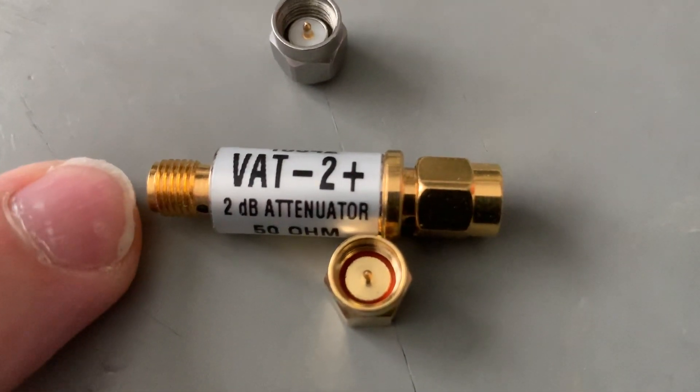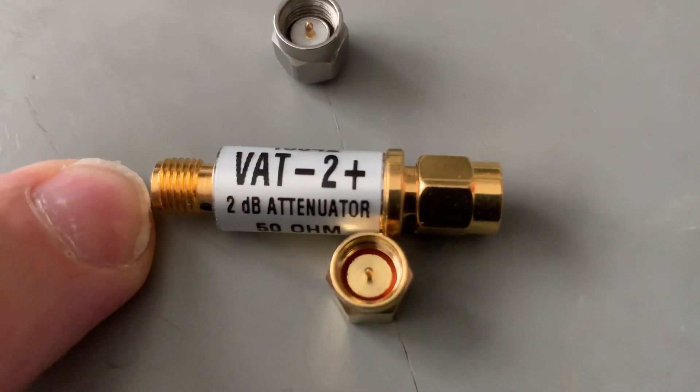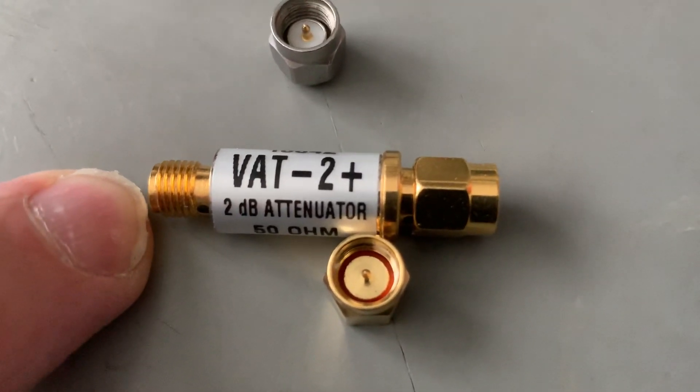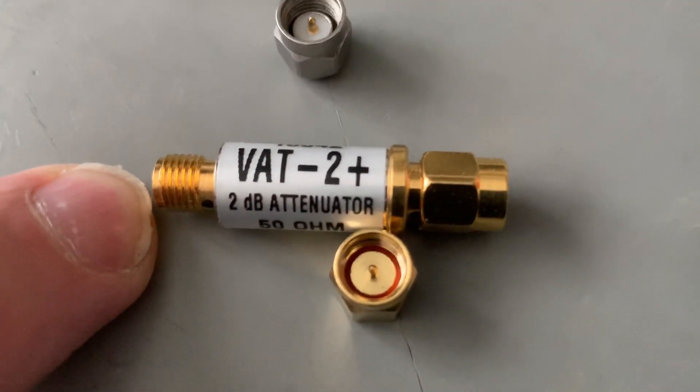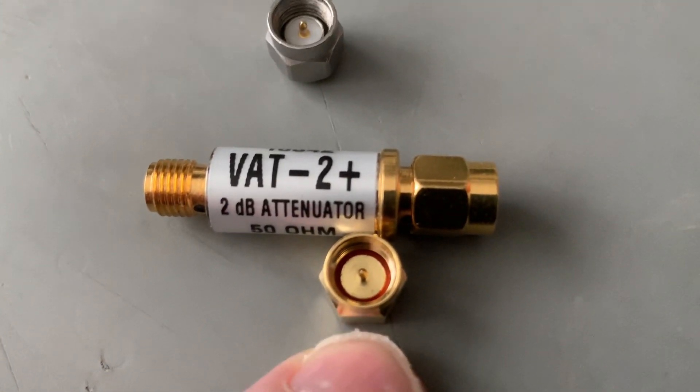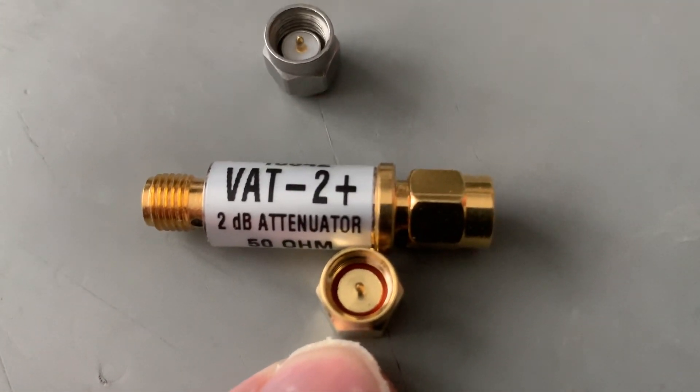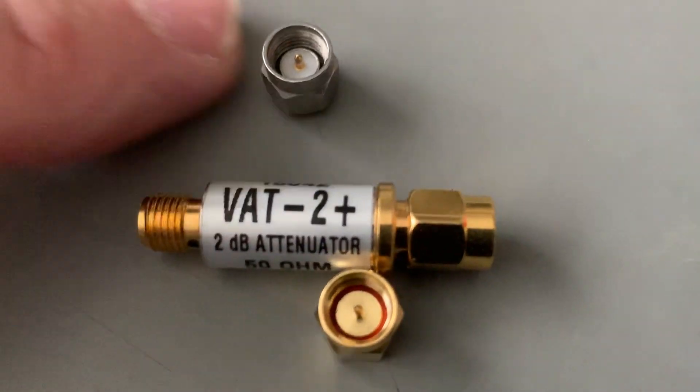In the middle here we have an attenuator, it's a 2dB attenuator, so if one end is left open it will have about a 4dB return loss. At the bottom we have a coaxial short.